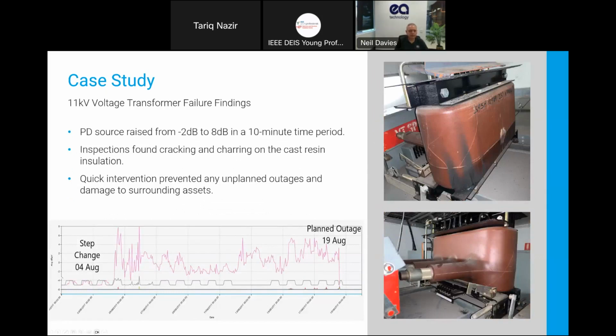We can see in the graph here, this is what was happening. So again, this is an ultrasonic source measured in decibel microvolts. We're reading negative numbers, which is very, very low or nothing effectively. And then on this one day, which is a Friday afternoon, it will always happen on Friday, we had a burst of activity. We went from -2 dB on an average to 8 dB on an average. That's quite high in terms of average numbers. And then the client was informed here.